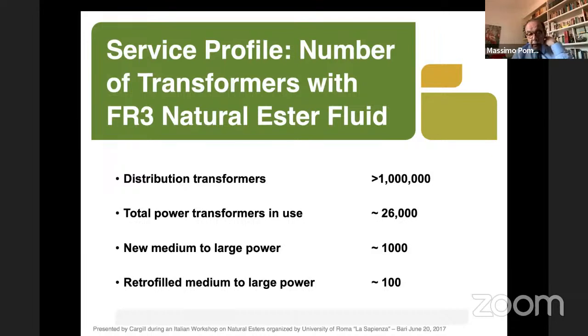Retrofilling is a special technique. It was not used everywhere in the world. In some countries, quite used. So it means that when your transformer started to become old, you open your transformer, you remove the insulation. Normally, you remove the insulating liquid, you change the oil, and so giving a new life for your transformer. And changing the oil, you can use, instead of mineral oil, you can use natural ester liquid.